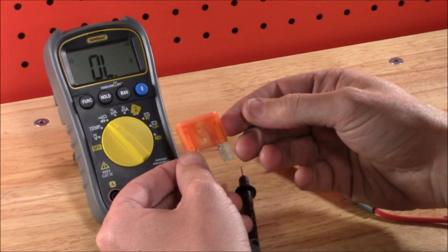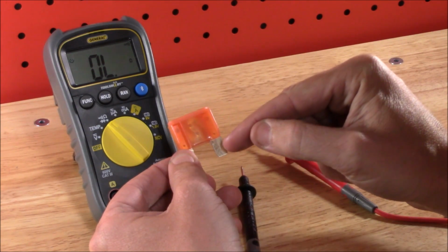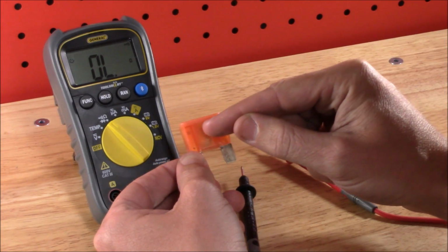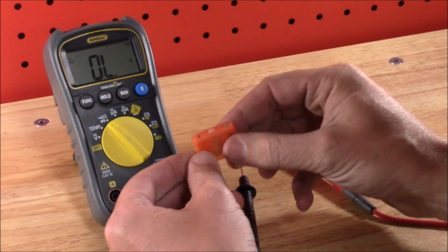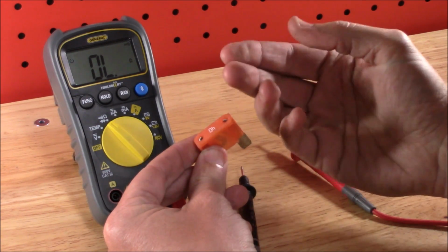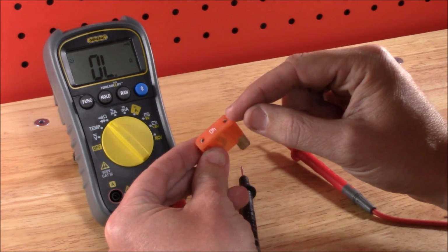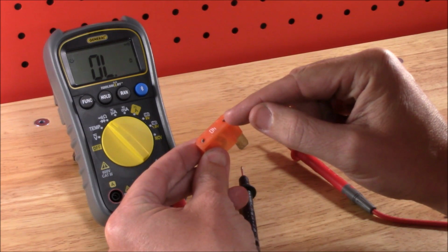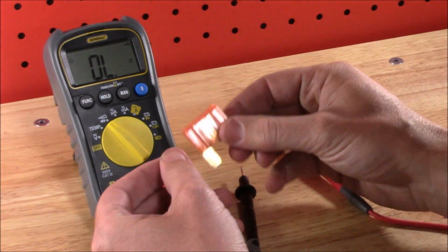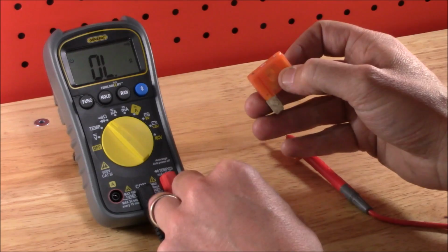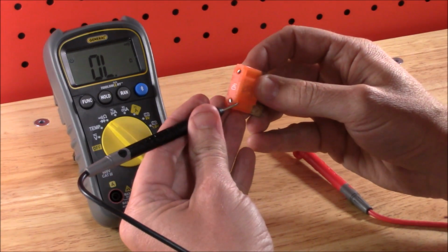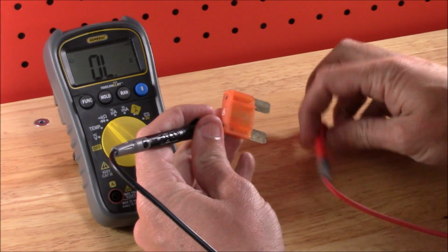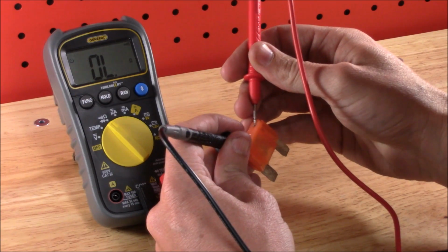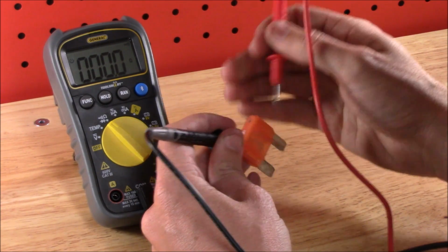If a fuse is damaged, one post is no longer connected to the other because the center portion has burnt out. Even if installed, we can put one probe against each pin on top, and if we hear an audible alert, the fuse is good. We'll take the black probe against one pin and the red probe against the other, and when we hear the alert, it means this fuse is still good.